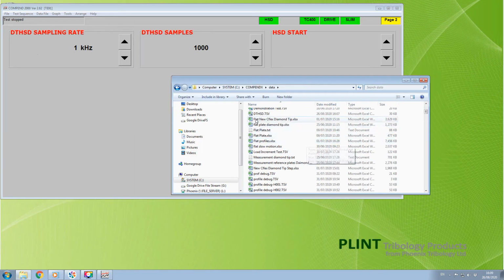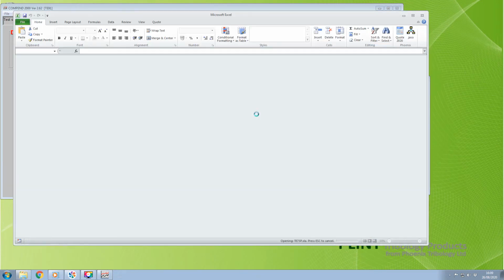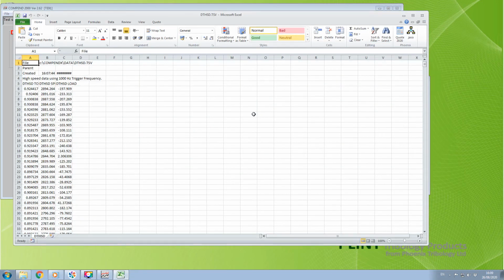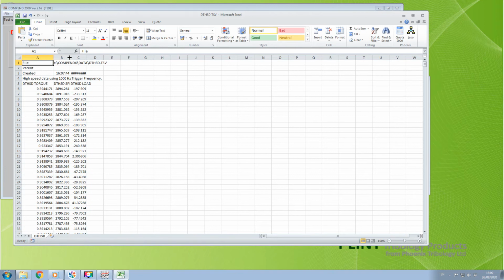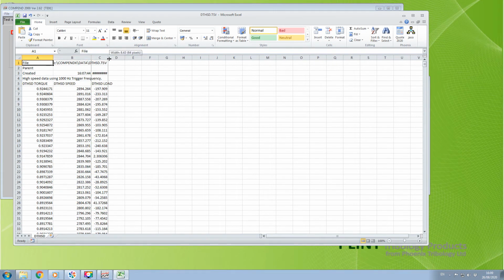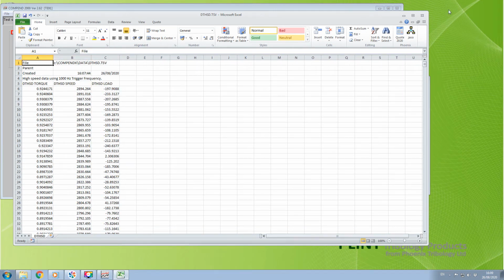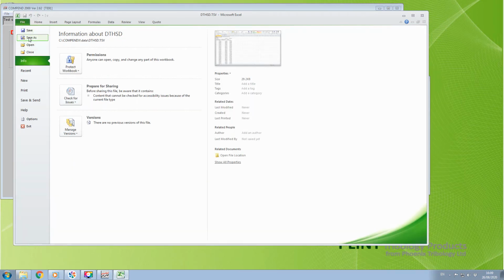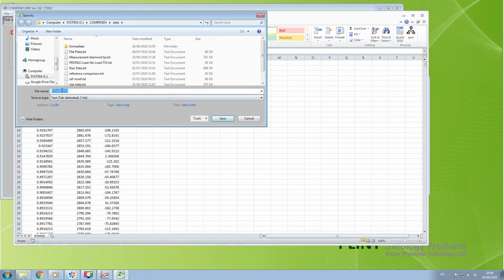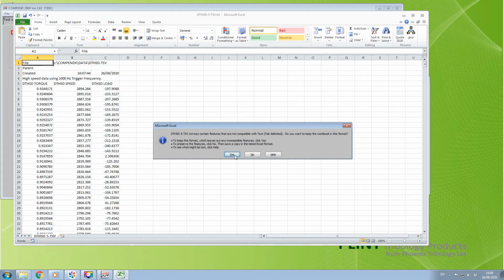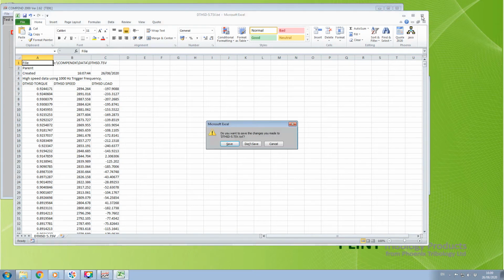The associated data file can be accessed from the C-Compendex data directory and is called DTHSD. In the case of the TU91, there are three inputs connected to the high-speed data acquisition interface: speed, torque, and load. Note that this file will be overwritten the next time manually triggered high-speed data is triggered. So if you want to keep the data, save the file under a new name.